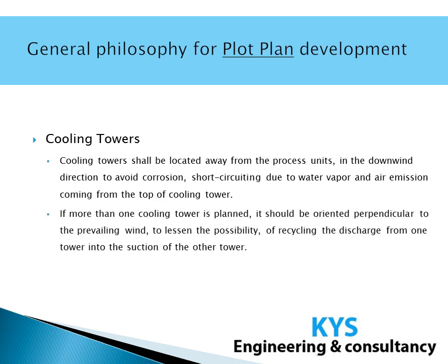If more than one cooling tower is planned, we must try to orient them perpendicular to the wind direction so that we can lessen the possibility of recycling from one cooling tower's discharge to the suction of the other tower, so that recycling can be minimized and we can achieve higher efficiency of the cooling towers.